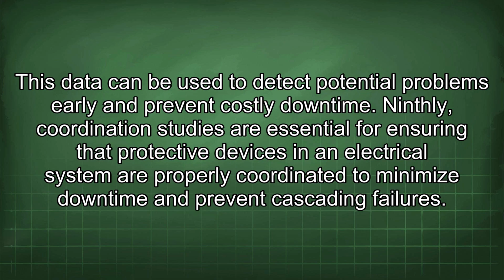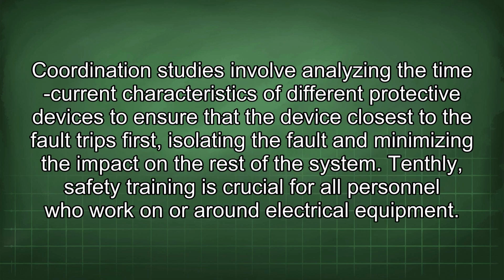Ninthly, coordination studies are essential for ensuring that protective devices in an electrical system are properly coordinated to minimize downtime and prevent cascading failures. Coordination studies involve analyzing the time current characteristics of different protective devices to ensure that the device closest to the fault trips first, isolating the fault and minimizing the impact on the rest of the system.